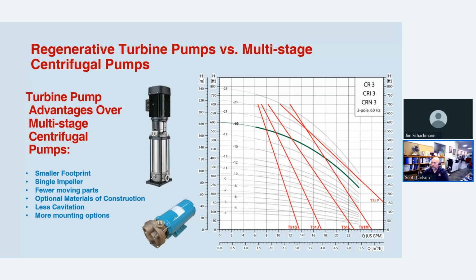So to compare that with a multi-stage centrifugal pump, in this example, we have 3-stage up to 25-stage, and then we have the MTH models. These are all single impeller models. So they're all one impeller and they can hit multiple spots with different models. Here we've got, as our example here, a 19-stage pump that we can hit any part of this curve in its preferred operating range with just a single impeller of one of our T51s. So for comparison, you would have this large vertically stacked pump for the multi-stage centrifugal versus just our single impellered pump and motor with our T51.